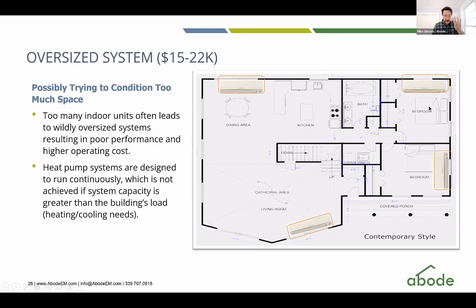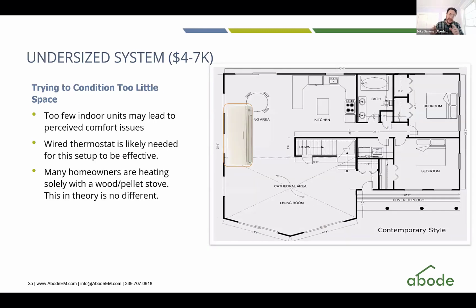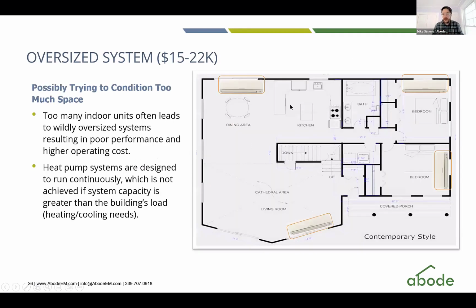So for this example, we have 4 ductless pieces of equipment. The smallest outdoor unit that supports 4 ductless units from a major manufacturer is 36,000 BTUs per hour. As I said before, in this example we have an 18,000 BTU load and an 18,000 BTU ductless system. The smallest piece of multi-zone equipment from a major manufacturer is 36,000 BTUs per hour, and that piece of equipment only modulates down to 22,000 BTUs per hour.